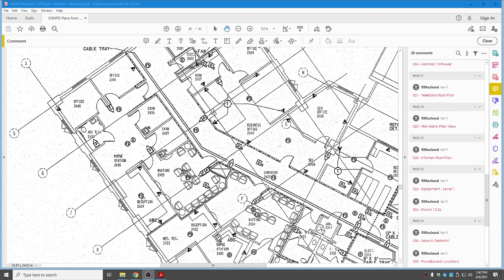Okay, then reception area, we have a speaker in the ceiling. We have a smoke detector in the waiting room, a speaker, a pull station, and a visual device, and a combination fire smoke damper on the return air duct, another visual device in the corridor, a duct smoke detector on the return air duct, and another combination fire smoke damper in the return air duct. Going down the corridor, you have your dual egress doors with a fire alarm pull station, visual device, duct smoke detector at the return air duct and the supply air duct. I think we've kind of covered enough when it comes to some of these symbols. Let's move on.